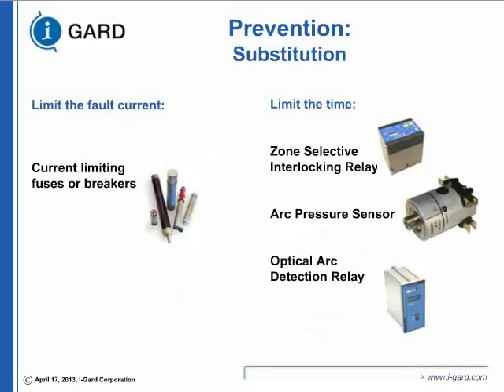Some devices are available to limit the fault current or limit the time. Arc flash is proportional to current and clearing time, so reducing either one can reduce your incident energy or the flash. On limiting the fault current, let-through current is limited by current limiting fuses or breakers. They operate very quickly, thereby let-through current is minimized and equipment damage and flash is limited. On limiting the time, you have zone selective interlocking relays, which have come recently. You can have arc pressure sensors and light detection relays. We'll try to address each one of them quickly.